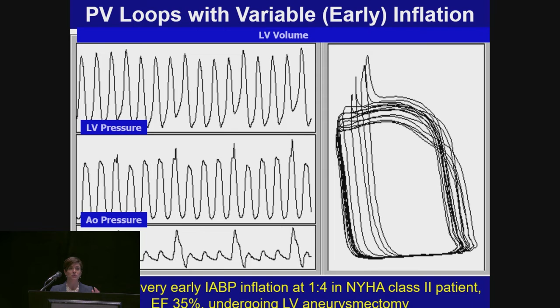Now, this timing error also is going to increase MVO2 due to the increase in wall tension and increased volume and pressure. Late inflation reduces the length of augmentation, but does not result in immediate negative hemodynamic changes. Over time, the reduction in coronary flow may be detrimental to balancing oxygen supply and demand, but we did not specifically study that here. We wanted to stick with what we knew was bad and look at that early inflation.